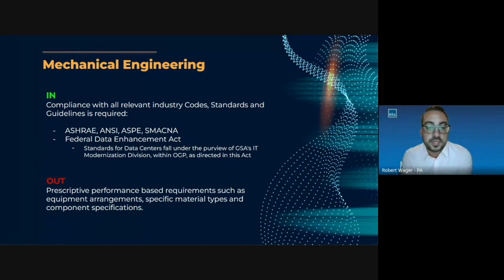What's out of the CBS is prescriptive requirements such as minimum chiller or boiler equipment quantities, redundant pump sets, and specific material types, say for piping of select hydronic systems. Those are no longer mandated, so we defer to our industry standards and codes for what is permissible in terms of equipment and material types.